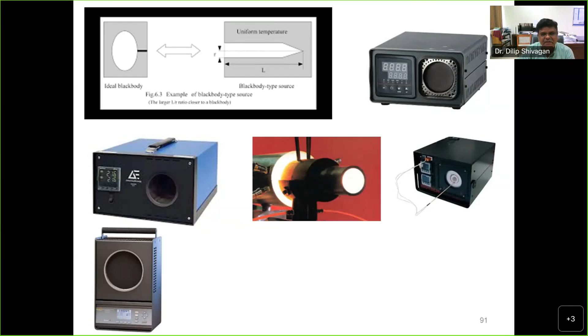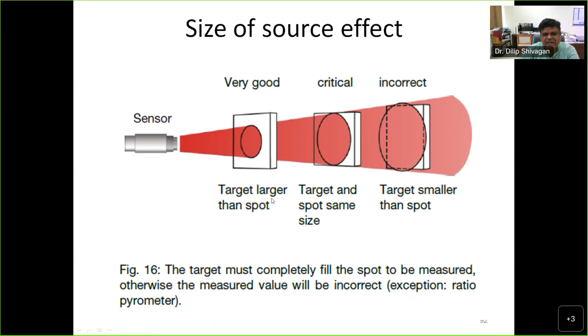So, size of source effect: because these sensors are not in contact with the object, they are not in thermal equilibrium with the object. They are photonic thermometers. So we need to see directly within the surface of the measurement unit, and we should not go away. There is a stated distance, a target distance at which we have to measure. That is given in your pyrometer. You have to carefully obey it.